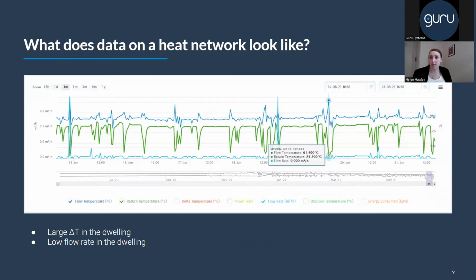We have some data here from a real system. You can see the flow temperature at the top in the dark blue. You can see the return temperature in the green, and you can see the flow rate or the load required in the light blue at the bottom. This is a healthy system. This is what a healthy system looks like. You have a nice gap between the flow temperature and return temperature, no matter what the load is telling us is going on. So this is what you want to see when you're looking at your data analysis from your heat network performance.